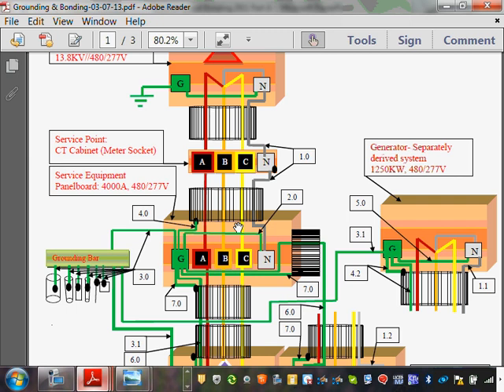Now when I reach this point here, this is my service, my 4,000 amp circuit breaker sitting here. I have my neutral bar, I have my ground bar. The first thing you need to do is create a grounding electrode system at the service. You guys, right? So the utilities have created their own grounding electrode system here. You are to reference to the same earth that we and the utilities share, the same ground, right? So I'm supposed to create right at the service a grounding electrode system to ground my service. Exactly like the utilities grounded their system, I am to create a grounding electrode system to ground my service. And when I ground my service, I ground everything else downstream.